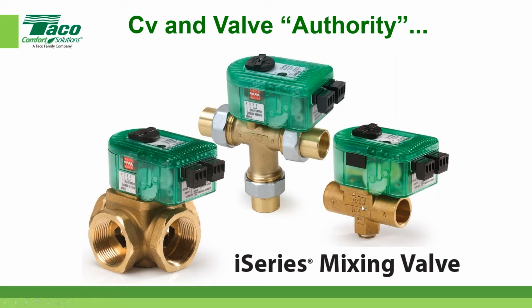And I'll throw one thing out there. The actual pressure drop of the valve itself, when we're doing mixing valves like I'm showing you here, here's a 2-way, here's a 3-way valve, here's a 4-way valve, the pressure drop of that valve on a particular system can be anywhere between 30 to 50% of the total pressure drop of that particular zone. So just put that in the back of your head, or make a note of it. When we push that to 30, 35, 40% of the actual pressure drop of the entire zone that pump's responsible for, we get really good valve authority. Okay, we get that valve to operate more correctly. The problem that we see with valves is not so much them being undersized, but often they're oversized because they're not using that principle I just told you about.